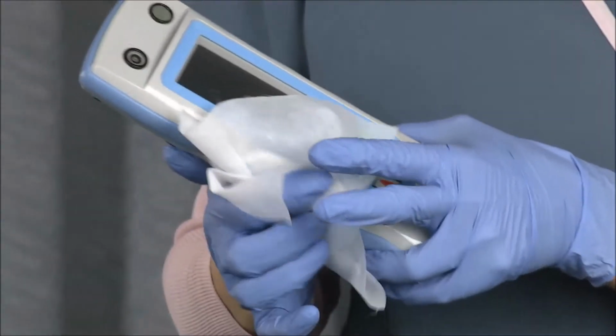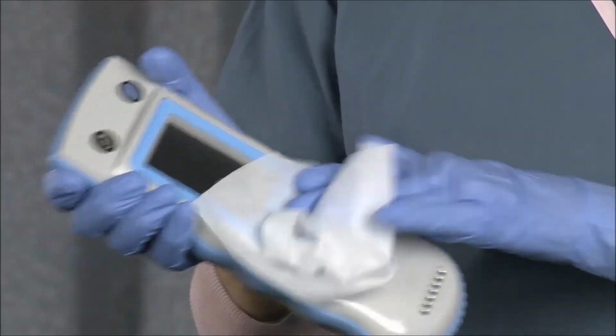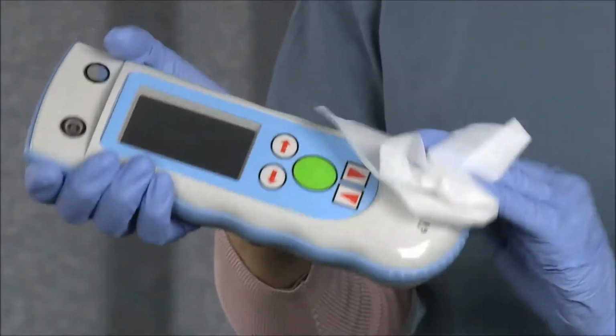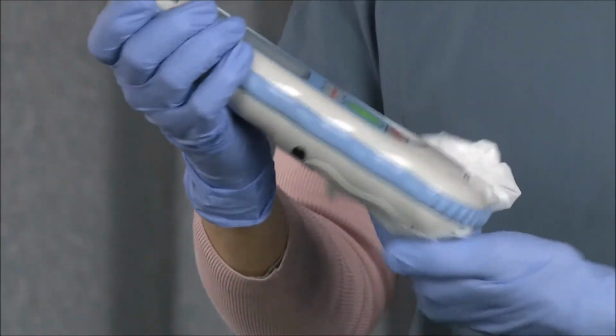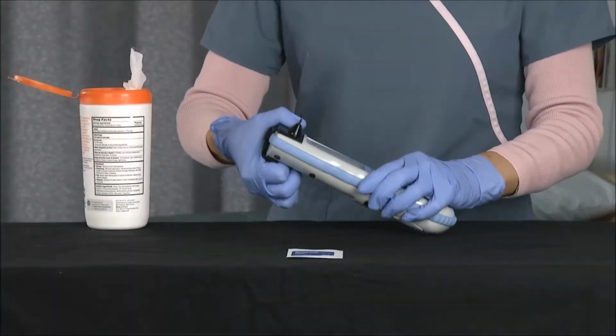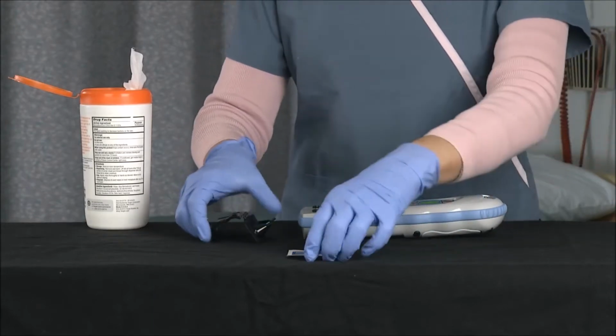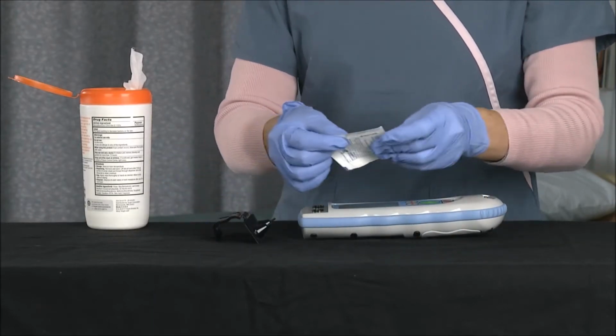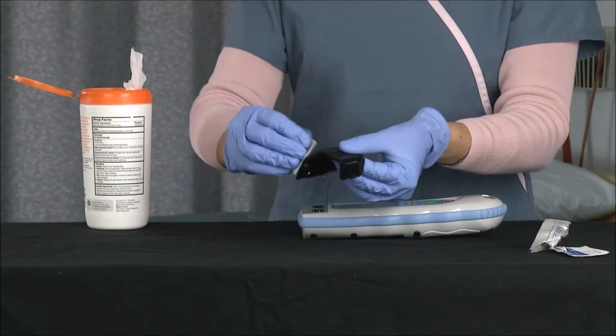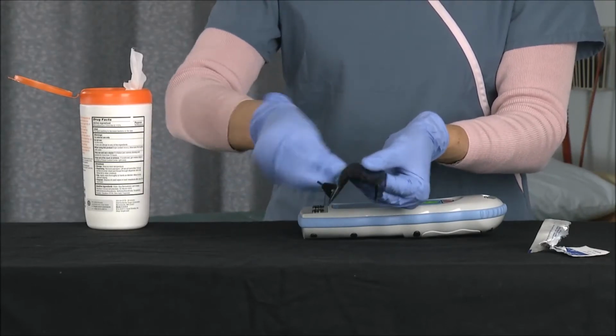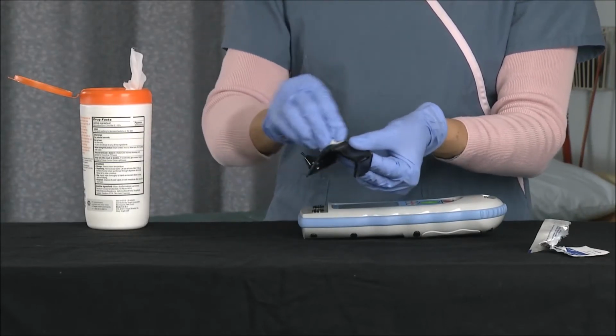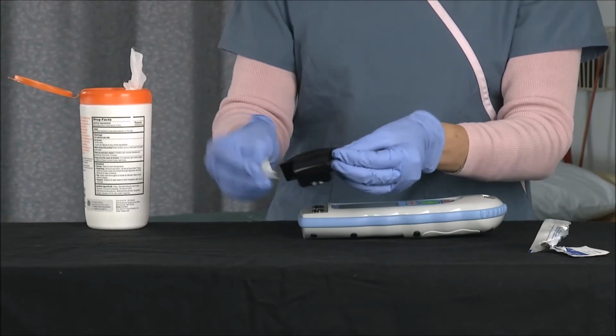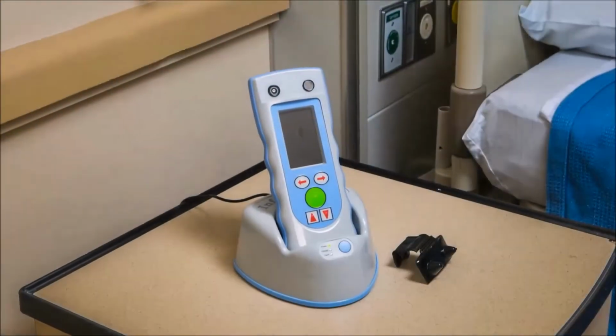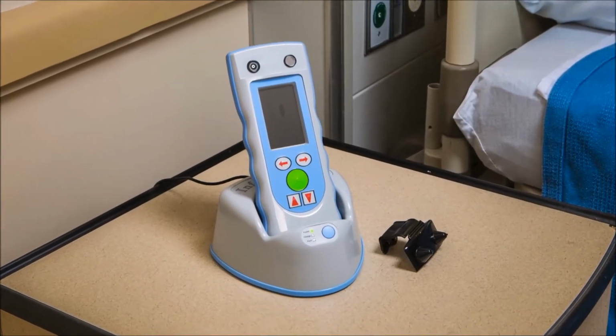It is important to clean the Infrascanner with an antimicrobial wipe after each use. To ensure the unit is completely clean, follow this simple procedure. Remove the disposable shield. Each disposable shield is approved for single patient use. A new shield must be used for each patient. However, you may clean each patient's individual shield with an alcohol swab after each use, and you can use the shield up to 10 times. Make sure to pay special attention to the tips of the optical fibers while cleaning. Store the disposable shield in the patient's area or room.